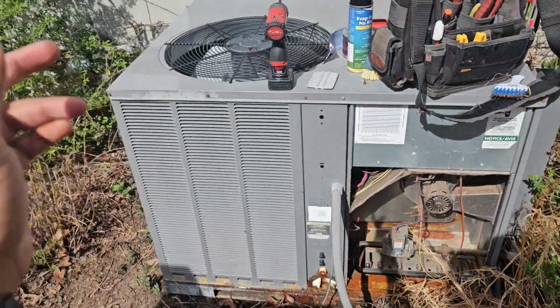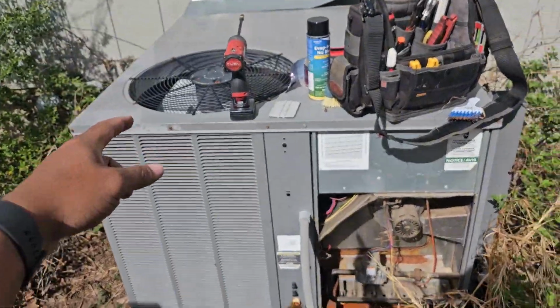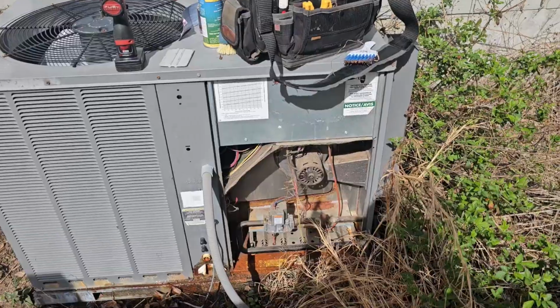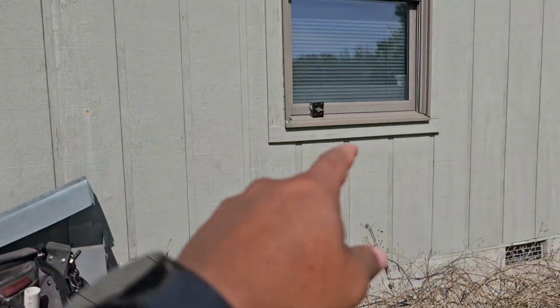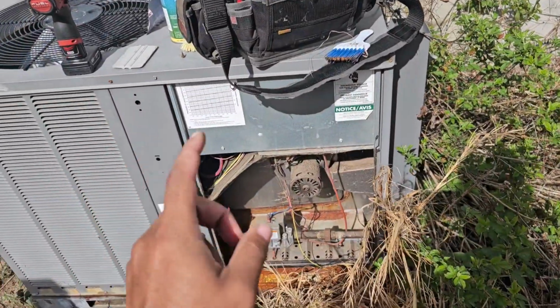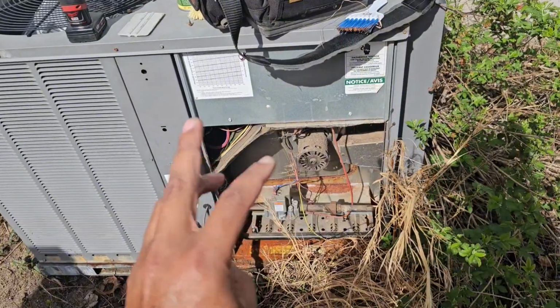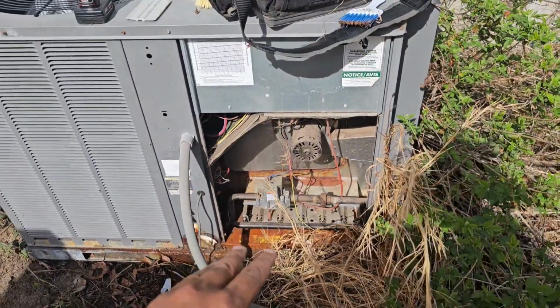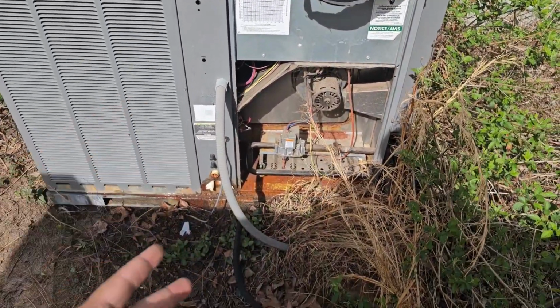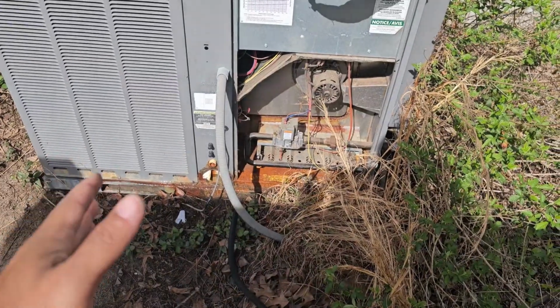I don't know the inside temperature, but I'll be able to tell once I get my probe on the return. I already got the disconnect pulled, sitting up there. I'm going to jump out R, Y, and G all together, so that way I know the fan's operating, the condenser's calling, and we're squared away to test the cooling.